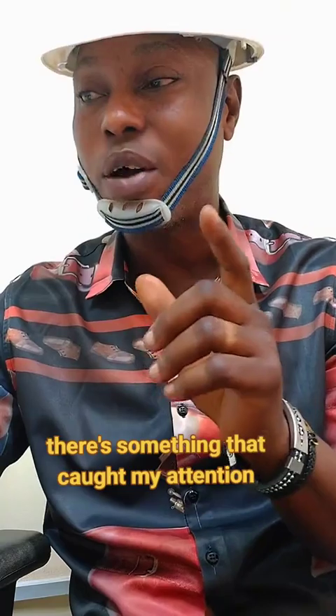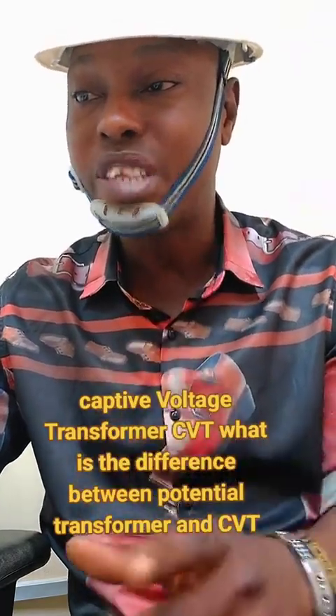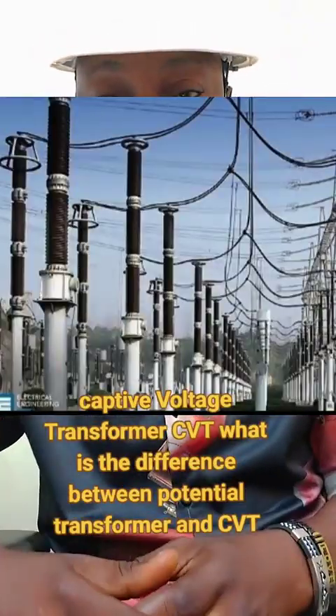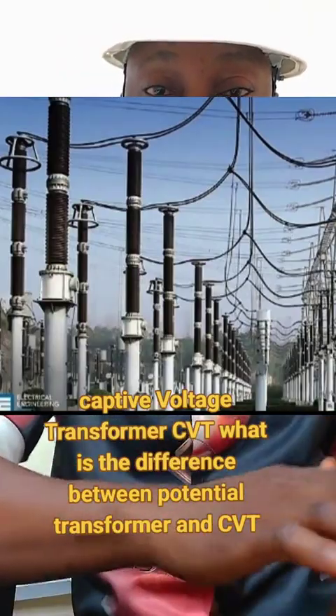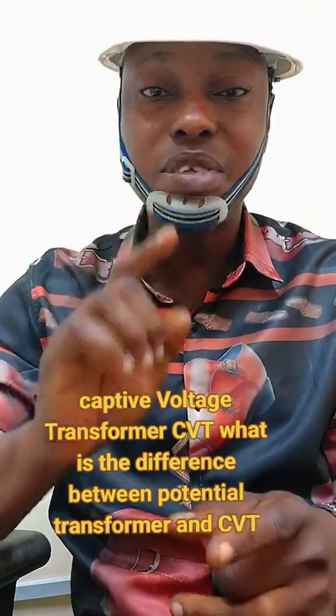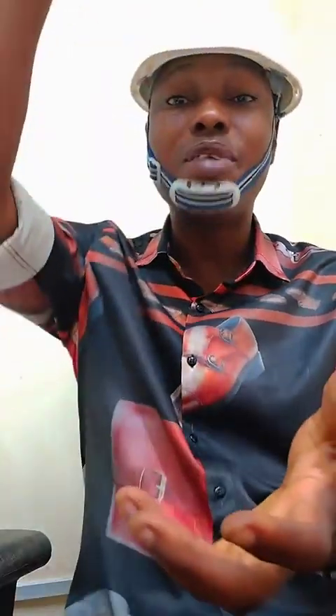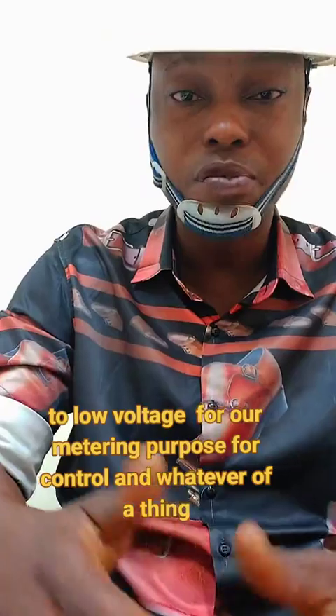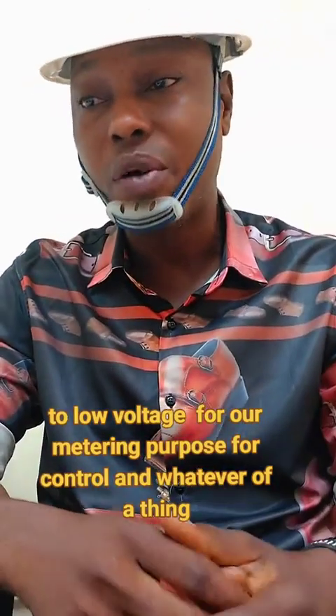We talk about strain insulators, which provide insulation between our conductor and our support system. And here there's something that caught my attention: the capacitor voltage transformer (CVT). What's the difference between this one and the potential transformer? The CVT works with high voltage, about 220 kV, 330 kV, unlike a normal potential transformer that works with our normal 11,000 volts. So all these are for protection, converting high voltage to low voltage for metering, for control and so on.